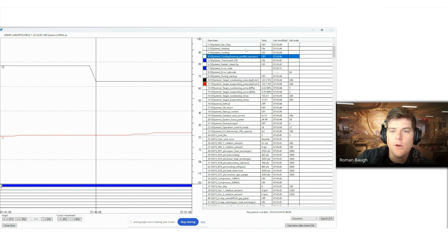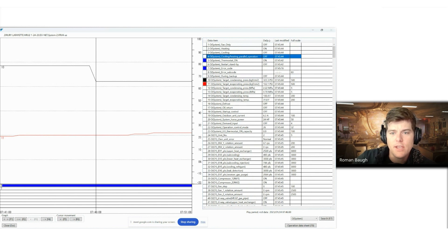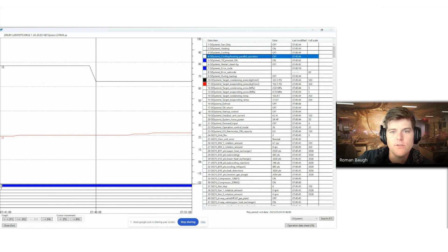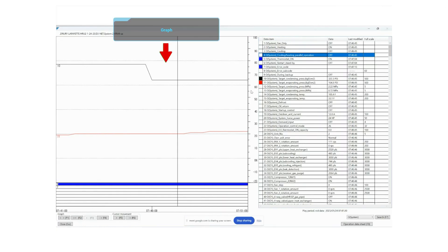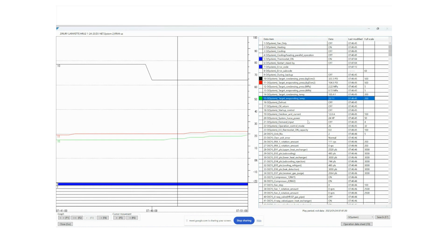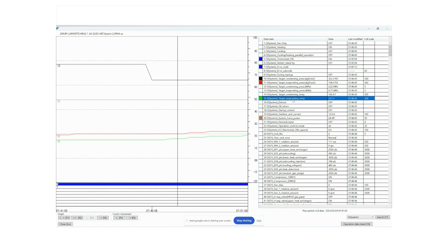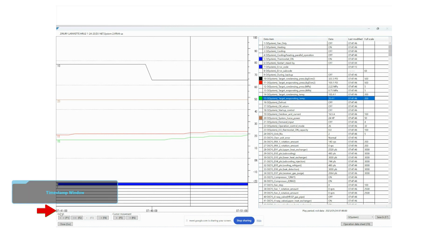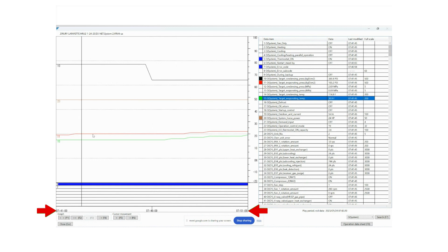Let's digress a little bit. So when we're looking at these line items and the data sets themselves, you'll notice also on the left hand side, we have a graph. And what that graph allows us to do is it allows us to plot specific points that we want to see over a specific period of time. So when we look at this graph on the left hand side, you notice I added system horsepower and I also added system target evaporating temperature. You can see as we roll through this and I click that they actually change numbers and they increase. Now, another important thing to know about the graph here on the left hand side is that at the very bottom is the timestamp window in which we're looking at. So on the far left hand side, this is 7:41 AM. And then on the right hand side, this is 7:51 AM. And so we're looking at a 10 minute window.